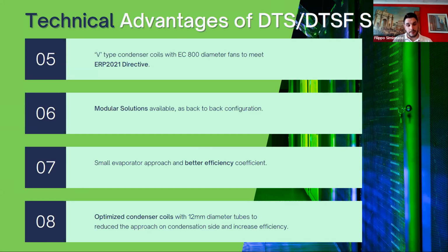This series, as I explained before, not only looks at data center applications, but is also designed for different markets. In this way, the DTS solution can also be thought of for different countries where there is a limit on refrigerant charge per circuit. In particular, we design modular solutions or back-to-back configurations using scroll compressors and low GWP refrigerant to meet the requirements, for example, of markets like northern Europe, Norway, Sweden, Finland, where the refrigerant charge for each refrigerant circuit must be lower than 10 kilograms.